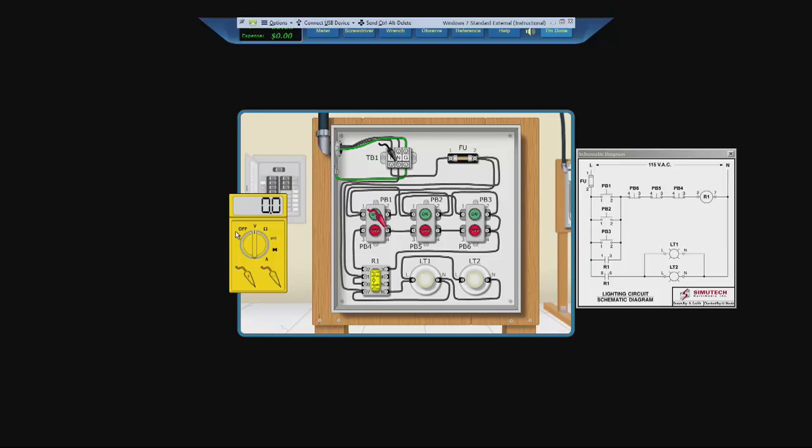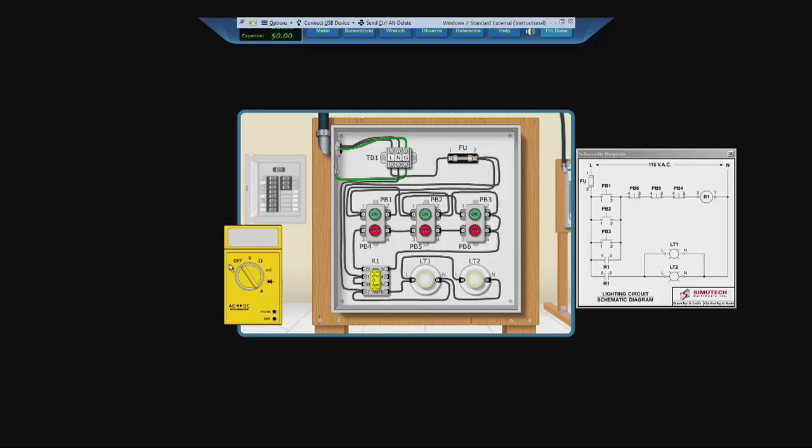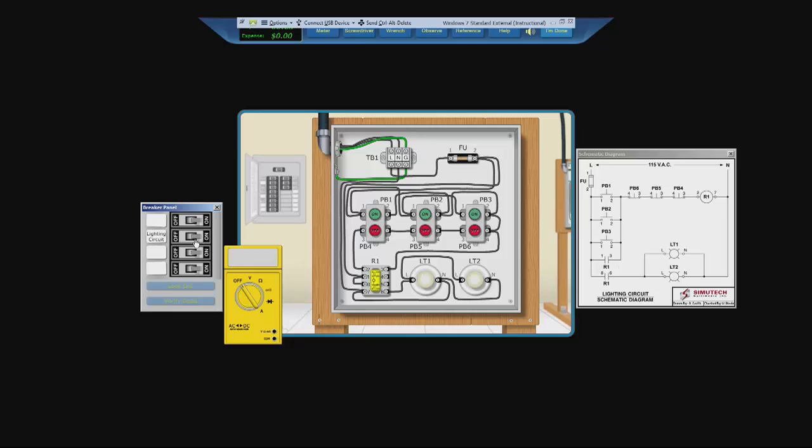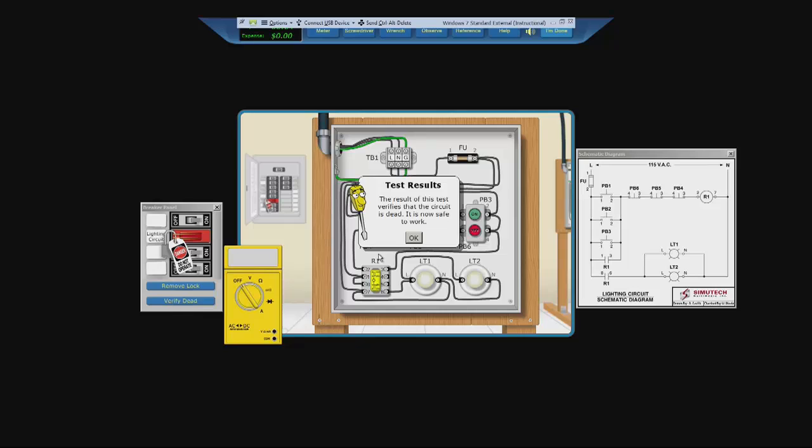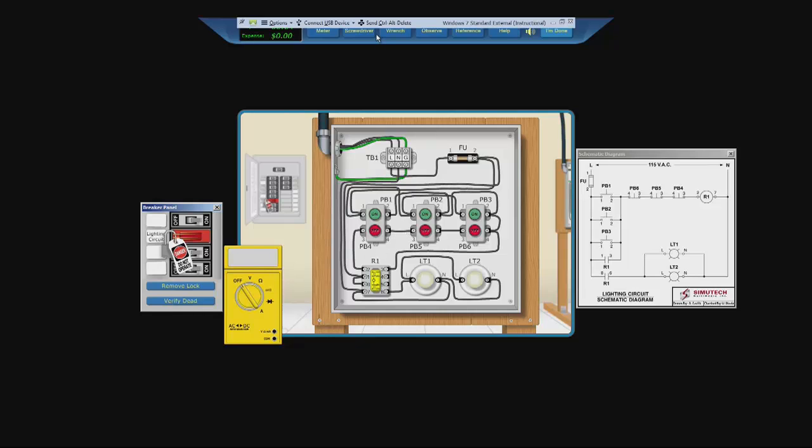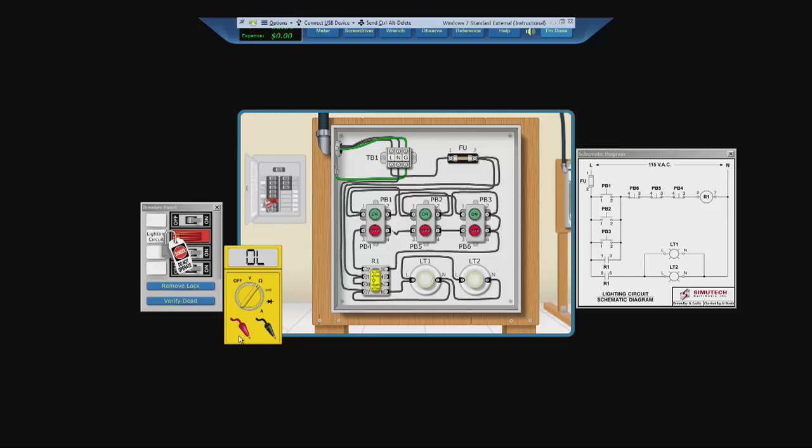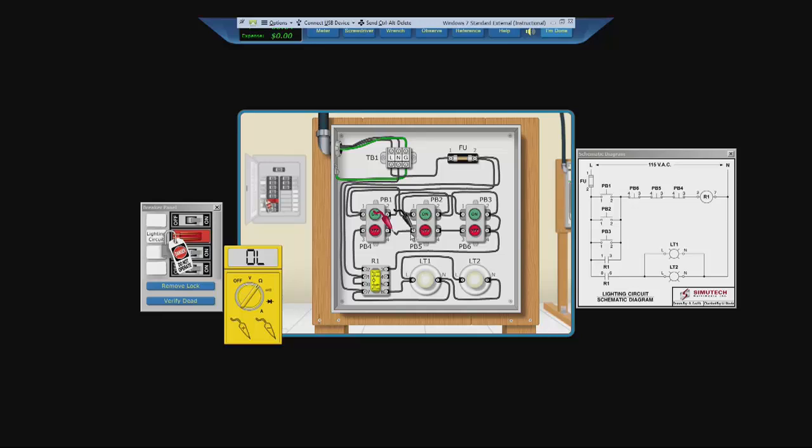So remove the lead by turning your meter off, open your circuit breaker, turn off the lighting circuit, lock out, and verify dead. Take your screwdriver and disconnect at one side of the wire in between PB4 and PB5. Change your meter to ohms. Put one lead on the disconnected side of the wire and the other lead on the other side of the wire. Open line.